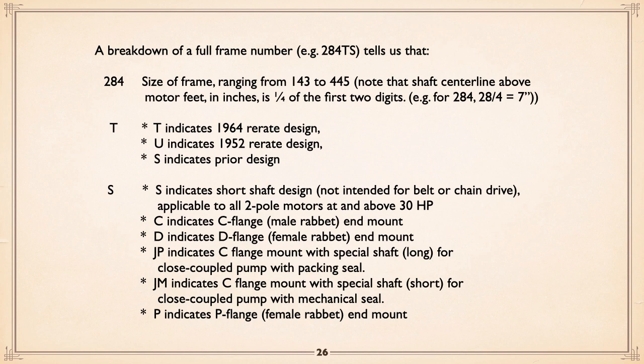You may find, if you have a number or a letter beyond the T, say a C, it indicates a C flange, which is a male rabbet. In other words, the inside sticks out, for mounting on different types of equipment. Some sewage pumps, if they're going to be externally motor driven, have a base for that. D flange is the same kind of idea, except it's a female. In other words, there's an indent on the flange for mounting.